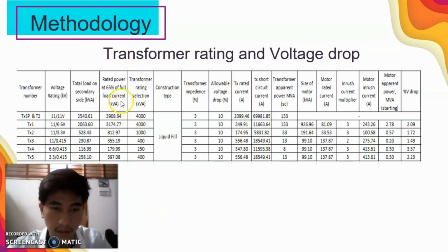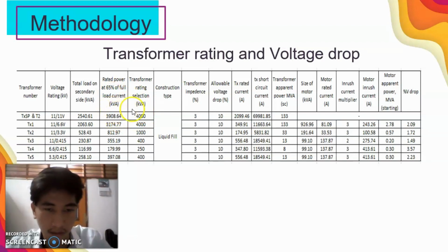Okay, next, identify the transformer rating and also the voltage drop. To fulfill the transformer rating, criterion 1 sets that the rated power at full load current kVA must be 65%. So this is the total kVA for all the distribution transformers, and we select the suitable transformer rating based on the rated power at 65% of full load current kVA.